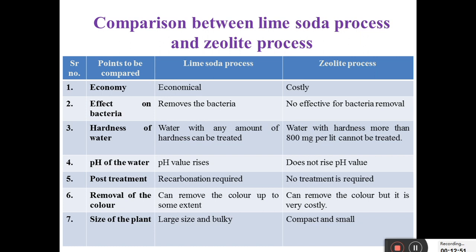Then the effect on bacteria. See, the lime soda process removes bacteria, and in case of the zeolite process it is not effective for bacterial removal. Then the third one is the hardness of water. See, water with any amount of hardness can be treated in the lime soda process, but in case of the zeolite process, water with hardness more than 800 mg per liter cannot be treated.